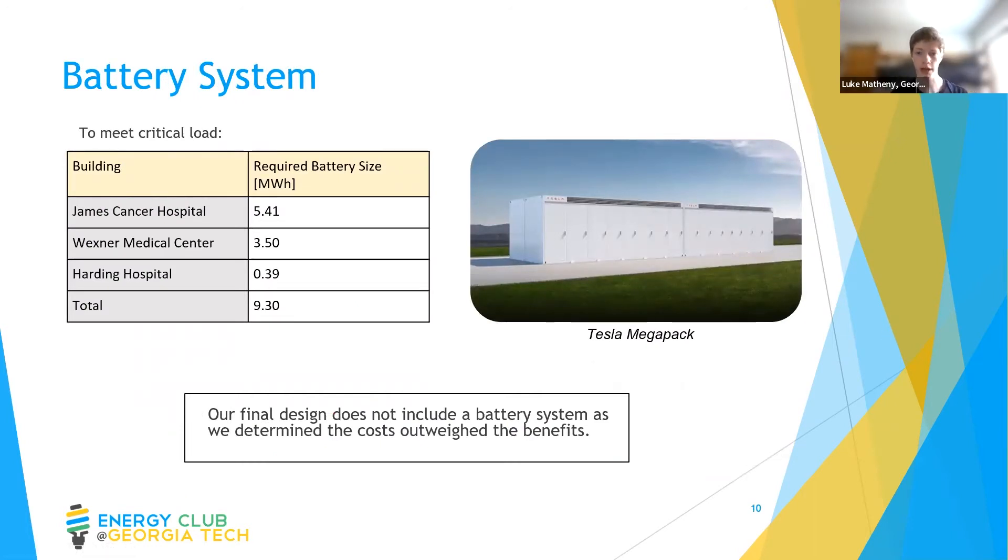Part of our design challenge was to include a battery that could sustain three of Ohio State's hospitals with 40% of their peak load in case of an outage. We found the average time for both local distribution outages and major transmission events, arriving at an average outage time of just over four hours. Multiplying those values together and accounting for load variance, we got a total of about 9.3 megawatt hours. Given this large number, we evaluated very large energy storage options. A Tesla Megapack is more economical than a series of smaller battery systems and is likely to use lithium iron phosphate cells, which we determined were ideal for our application. However, in our final design we chose not to use a battery system on campus because of its excessive cost compared to backup power generators, which would provide the same resilience.